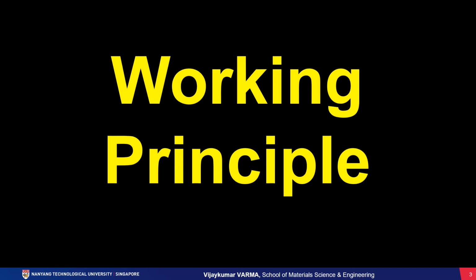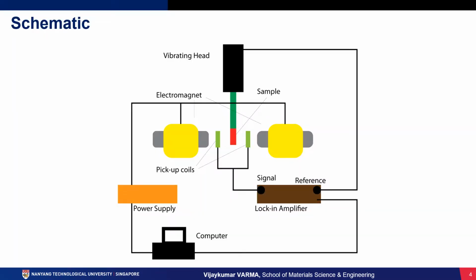So let's understand the working principle and some of the main components of the system first before going into the VSM demo. The main components of a vibrating sample magnetometer are an electromagnet with two pickup coils, then a vibrating head. This vibrating head is connected to the sample holder, so the sample holder oscillates due to this vibrating head, and it is connected to a lock-in amplifier to refine the signal which is obtained from the pickup coils.